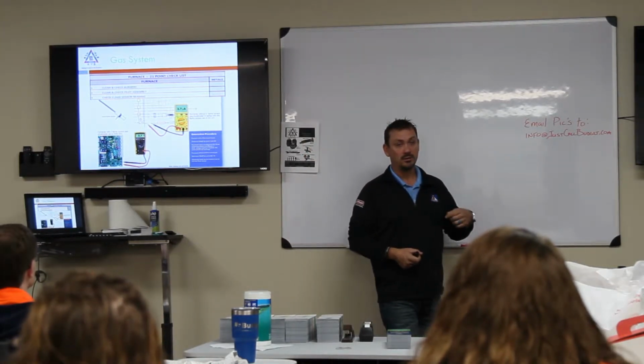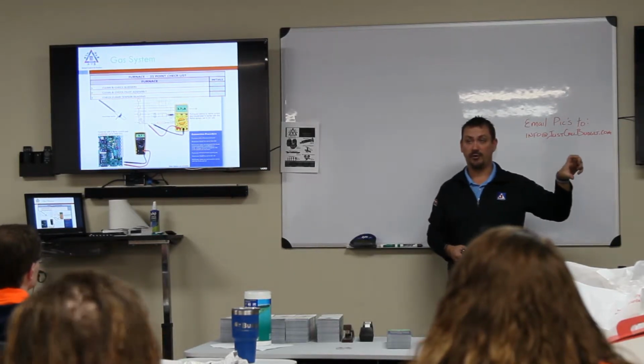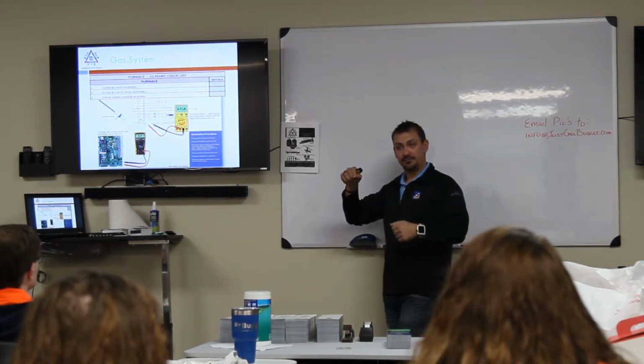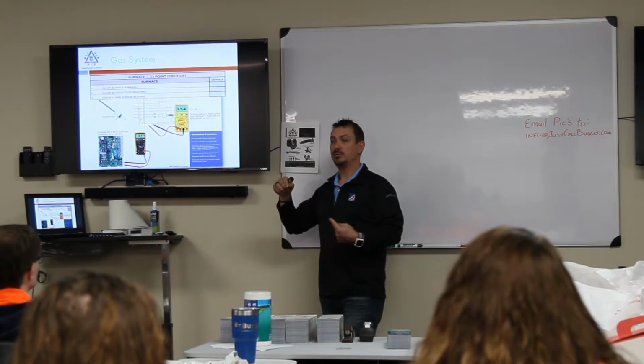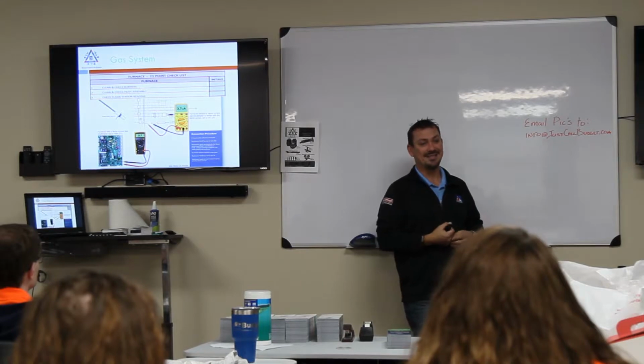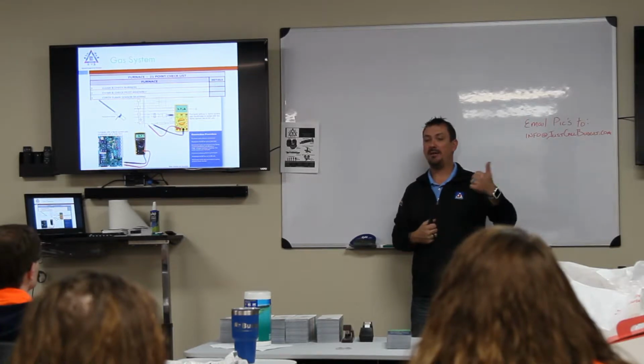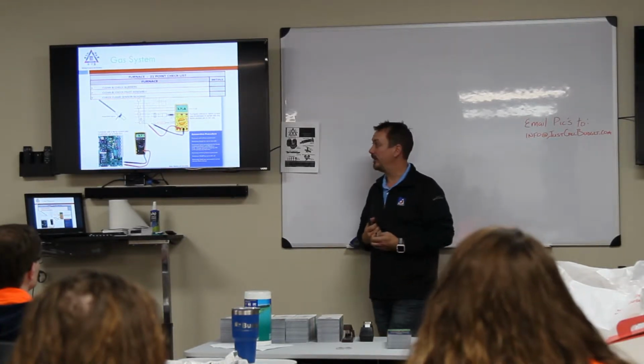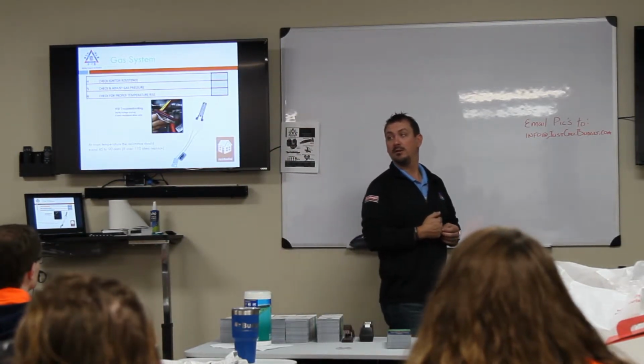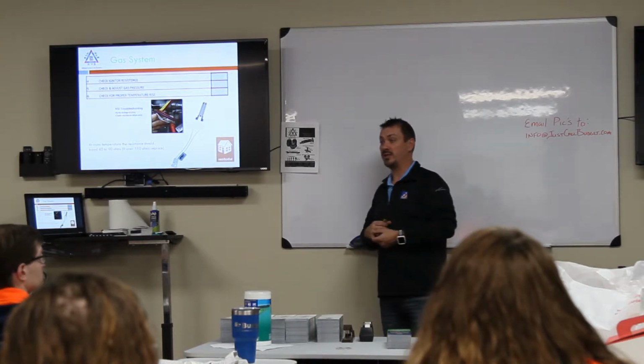And to test that, you're going to go ahead and take the ground wire that's in the electrical panel box on the furnace that comes from the breaker box, unhook that, put your lead there, and then your other lead on your neutral, and that's coming in from the panel box and that's hooked up to the furnace, and you should see less than 0.5 volts. 0.5 volts or higher means an improper ground, and we have to have that taken care of back at the breaker box. I'm sorry? I thought it was 0.2. It's 0.4 is acceptable. Okay. 0.4 or less.